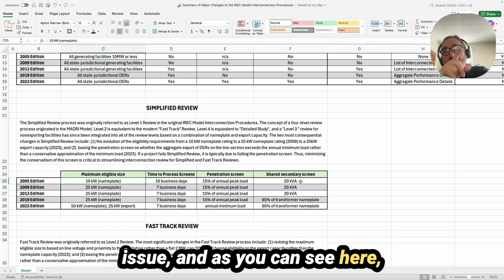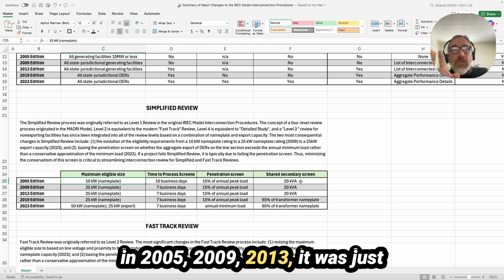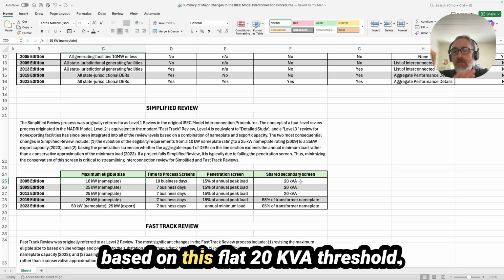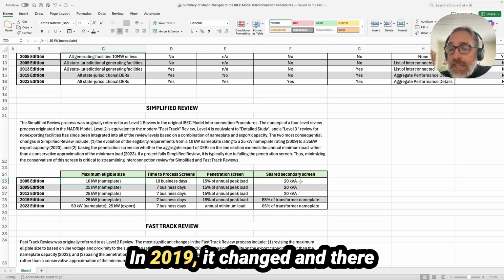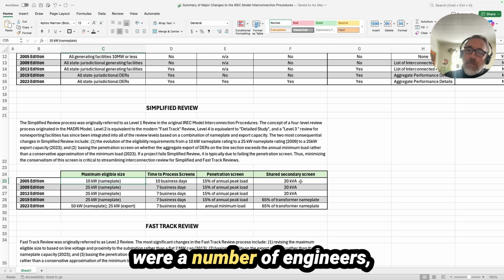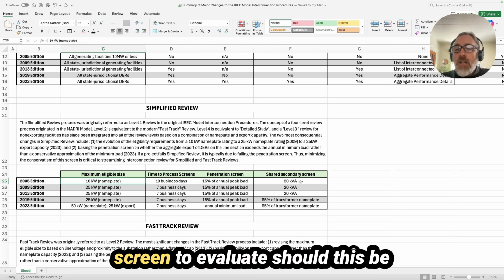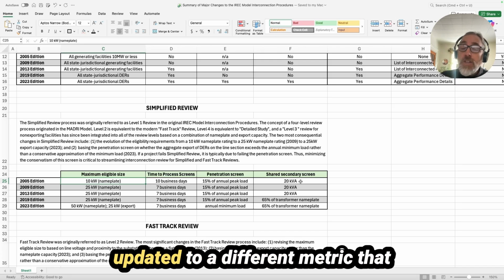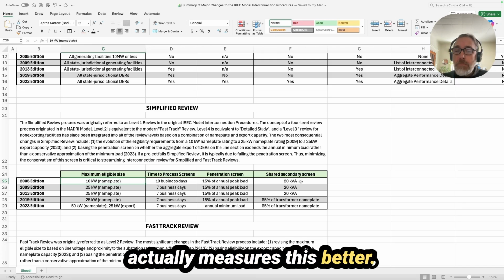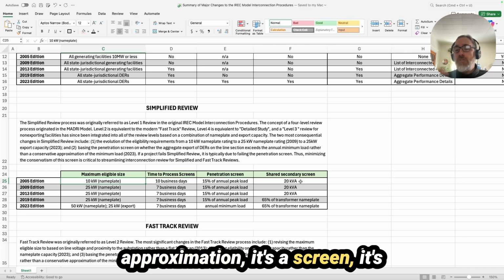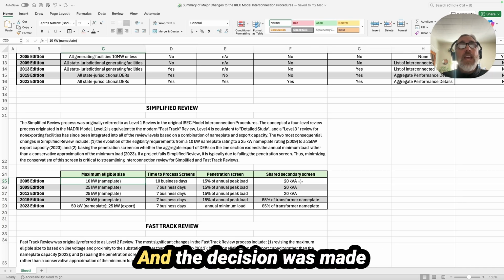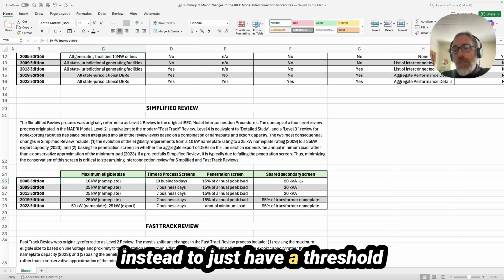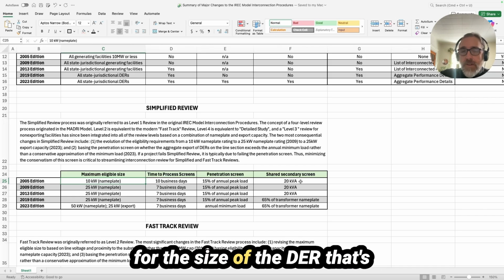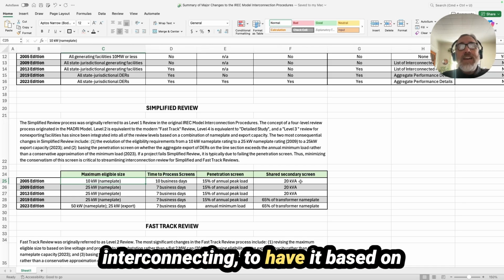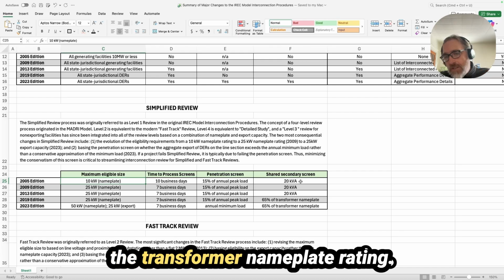And as you can see here, in 2005, 2009, 2013, it was just based on this flat 20 kVA threshold. In 2019, it changed, and there were a number of engineers, et cetera, that looked at this screen to evaluate, should this be updated to a different metric that actually measures this better? And again, this is an approximation. It's a screen. It's not an engineering analysis. And the decision was made instead to just have a threshold for the size of the DER that's interconnecting, to have it based on the transformer nameplate rating.